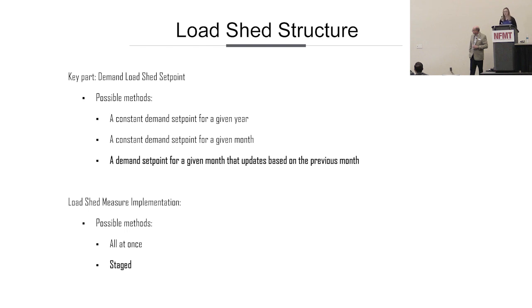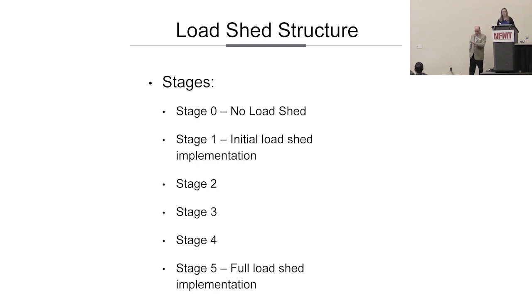Another thing that we had to consider is, do we want it's all or nothing load shed, or do we want to stage it? And we did end up going with the staged method because we didn't want to cause the facility manager and all his guys to have a bunch of complaints when the occupants in the offices don't know what load shed is and don't know that it's actually being implemented, and then he's getting 20 calls because the air feels a little bit warmer or the fan slowed down, and so it feels like less airflow. And so we tried to stage it so much so that it was very gradual and it wasn't as noticeable. And along with that, if we can do less but accomplish the goal, then we win. Because if we don't have to do all of what's involved with stage 5 and we can just do stage 1 and still keep that load down, then that was great.